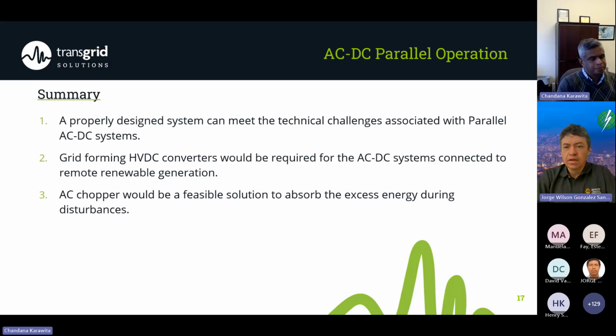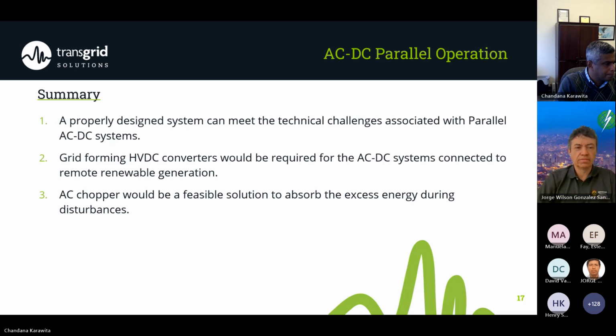Okay. The next question: in what type of scenarios is this situation, an AC to DC fault, prone to happen? Are there any scenarios that are of interest for such a fault? Yeah, you have to look at your corridor, how you have the two systems. If the two systems are going in parallel continuously, the possibility of having an AC to DC fault would be very low, because it would require the collapse of a tower or something. So then it is not applicable.